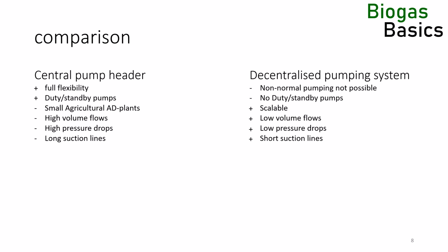In conventional applications, a pump can cavitate if the pressure drop on the suction side of the pump becomes too high. The required net positive suction head, or NPSH, must be smaller than the available net positive suction head to prevent a pump from cavitating. NPSHA must be larger than NPSHR. The phenomenon changes when digestate is pumped.